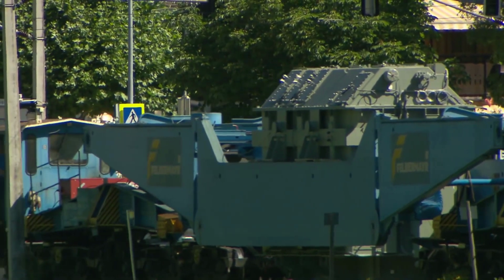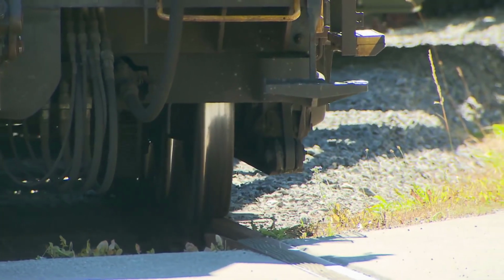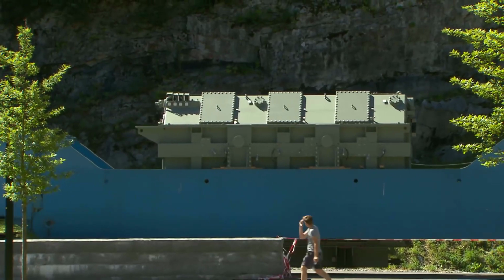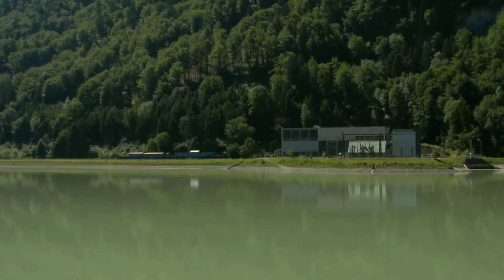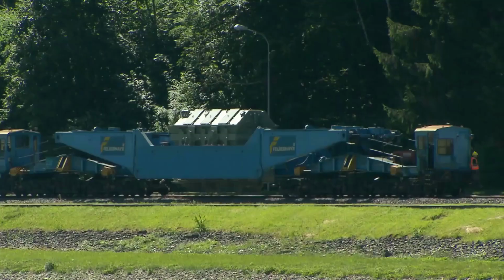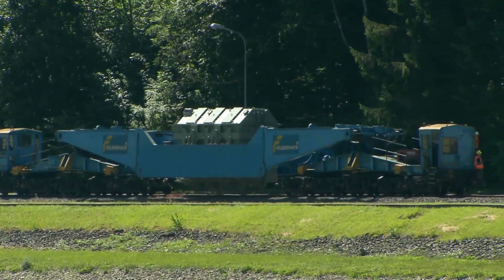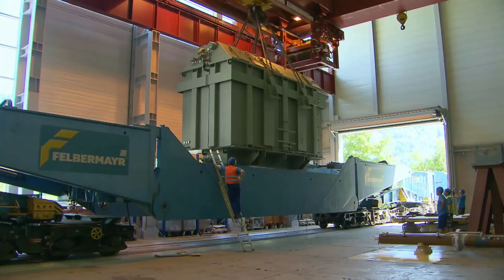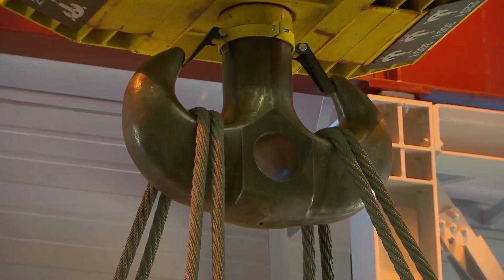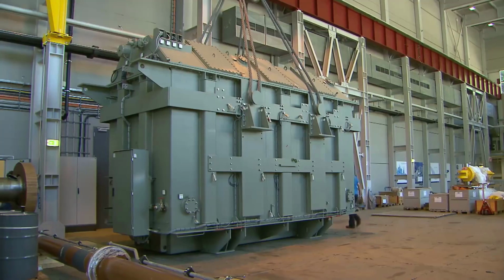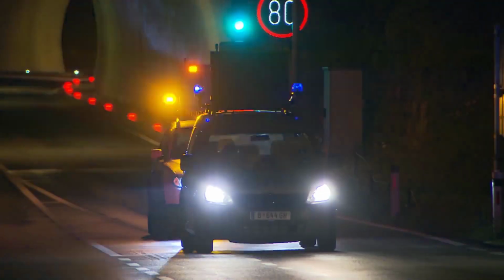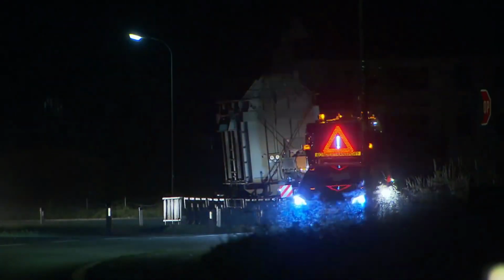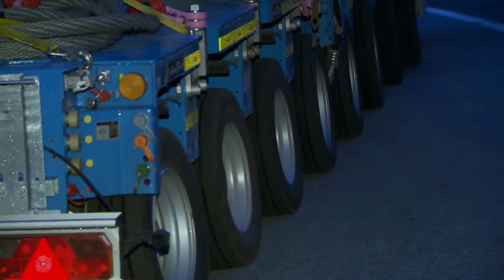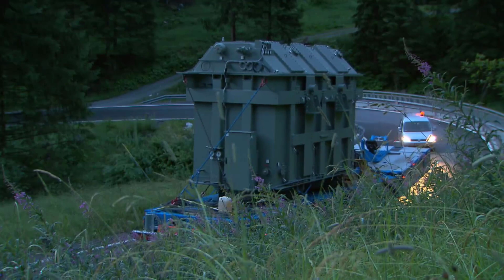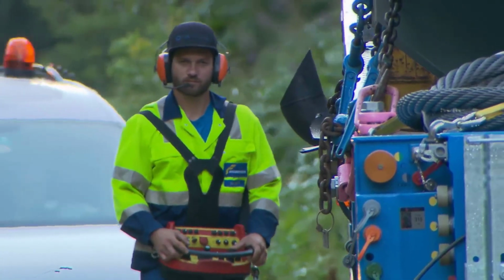Transformers convert the energy provided by the power plant for the high-voltage grid or absorbed from the grid to the respective voltage level. For the generators in the power plant, this is 14,000 volts, and in the lines up to the Burs substation, it is 220,000 volts. However, the transformer is far from finished, as many components, such as the cooling system lines, expansion vessel, and isolators, can only be mounted now to avoid making the transformer too large for transport.